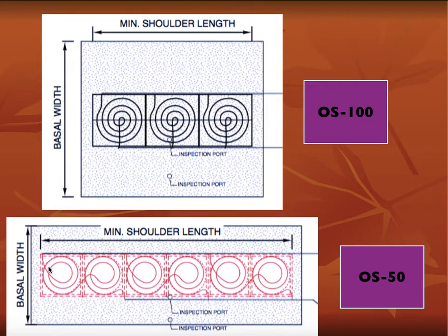Okay. So you'll see that this first coil has a connection to your supply line, and then the other end of the coil is attached to the coil next to it, and the end of that coil is what goes into the flush. So when the pump kicks on, it's going to supply both these coils before it goes to your flush line. And so that makes these two coils one lateral because they're hooked up together before the connection of a supply and flush is complete.